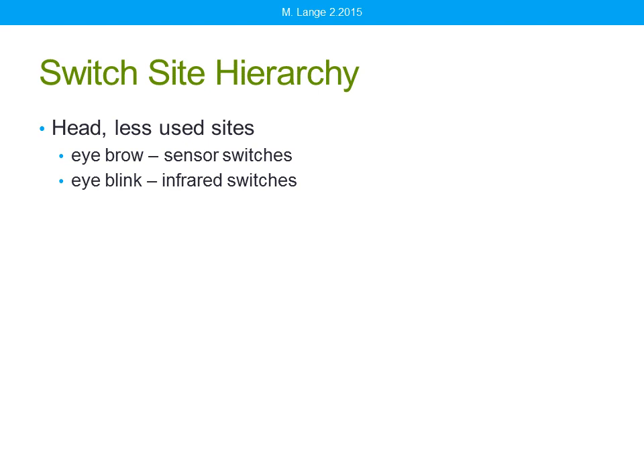Less-used but helpful sites include at the eyebrow using sensor switches and eye blink using infrared switches. For eye blinks, you definitely want to use infrared — fiber optic light can be damaging to the white of the eye, so do not use fiber optics for eye blinks. Infrared is safe to be directed towards the eye.